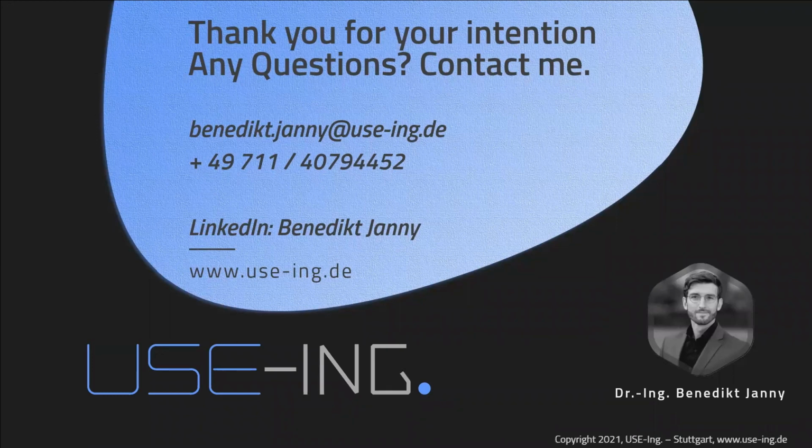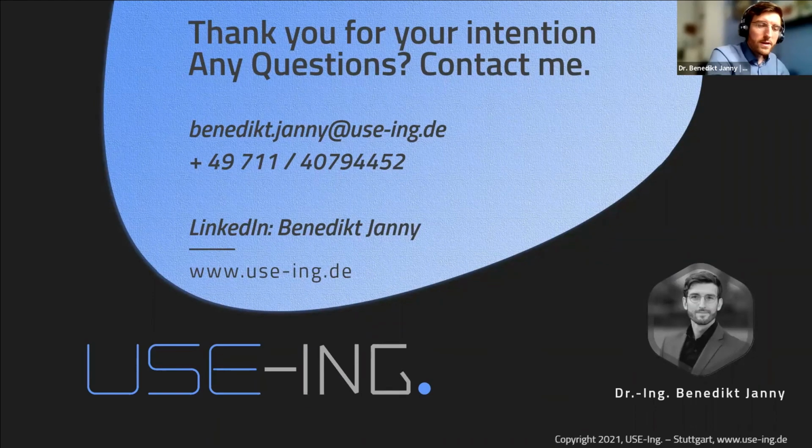Great. I have another question for you here. Is the purpose of 62366 mainly usability contributing to safety, or is it about designing a user-friendly medical device in general? In the old version, there was a first version of 62366 from the year 2007. At that point, it was not divided yet. With the 2015 version, you have a 62366 part 1, this part is the standard, and this is obligatory, basically focusing on effectiveness and safety.